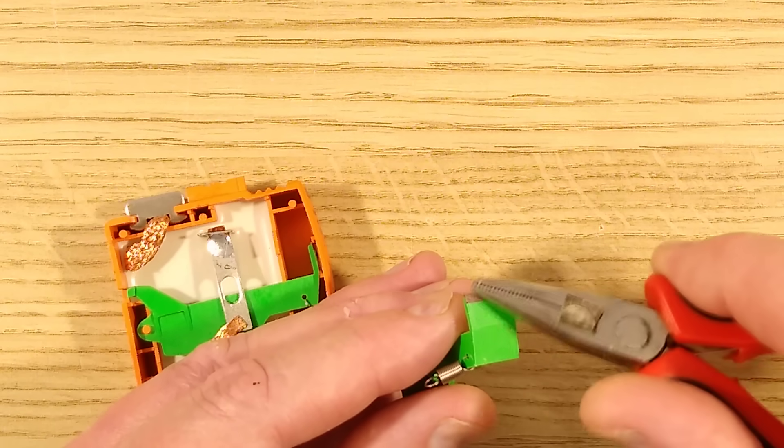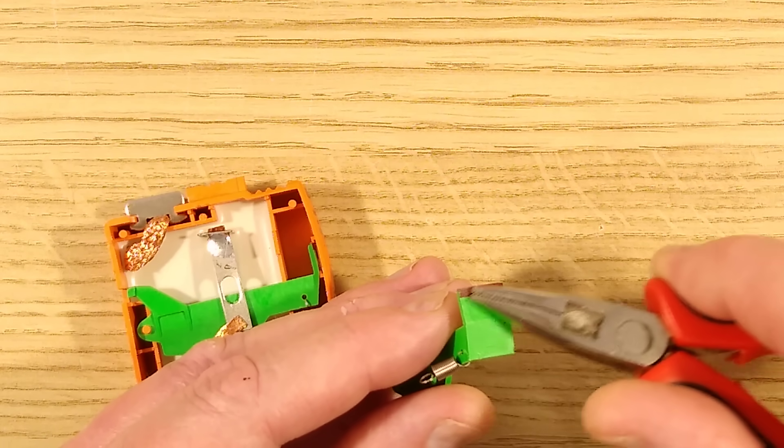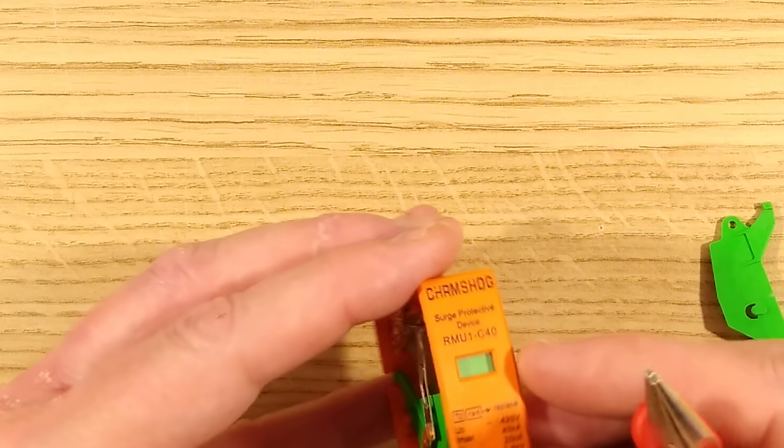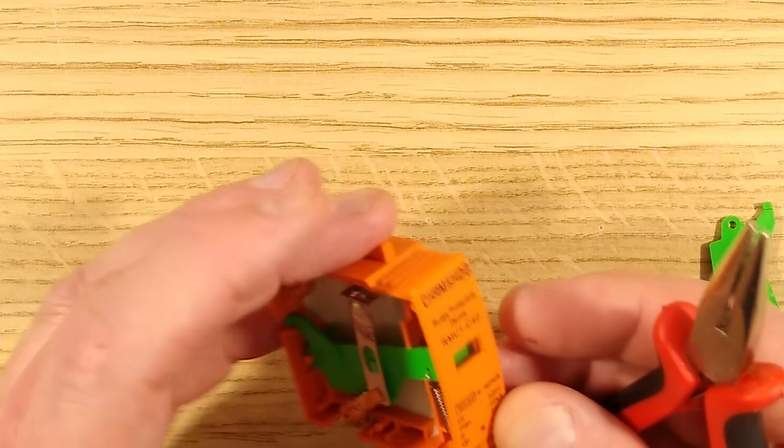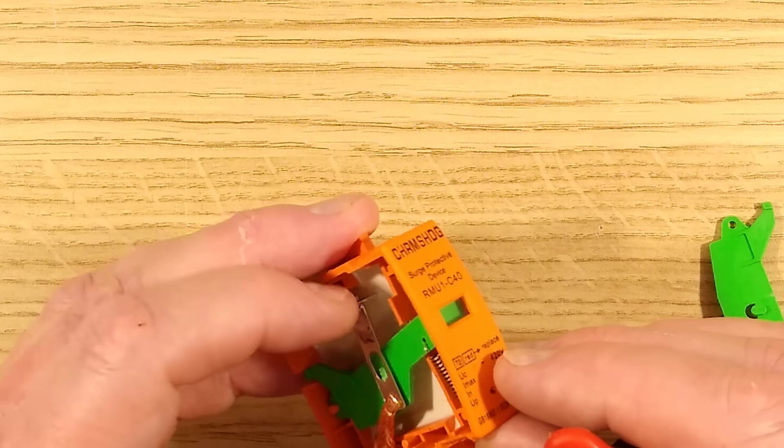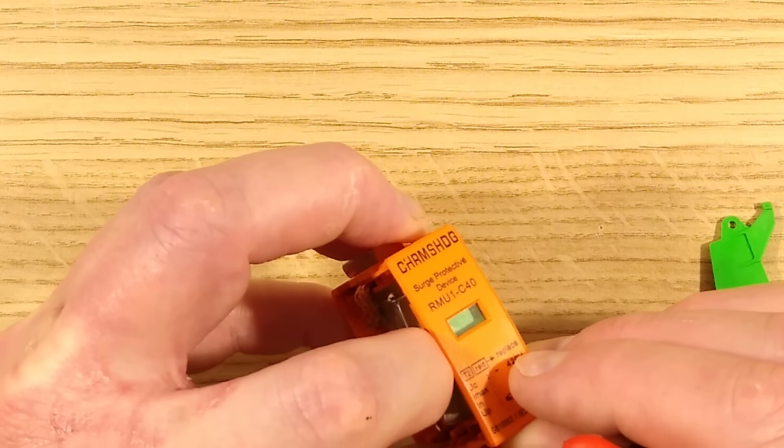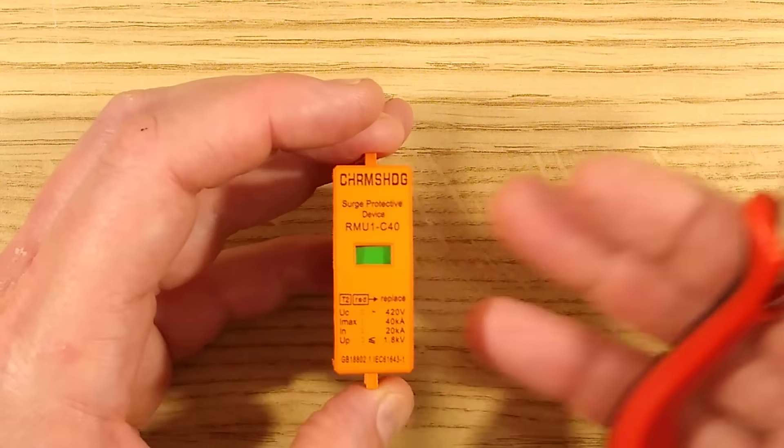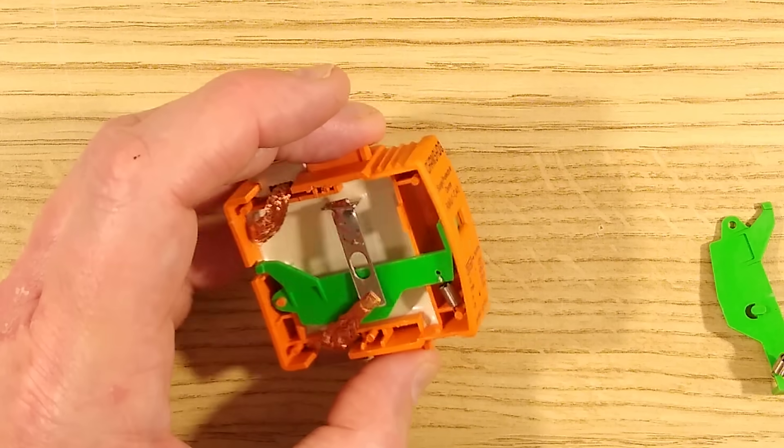And the reason for that is because this is a bad batch. This whole top window is supposed to be printed red, but they've actually just printed a red line in it. So in its latched state, it's displaying green. But also in its unlatched state, it's also displaying green. And it would indicate that it was good when it's not, when actually the protection has been lost.